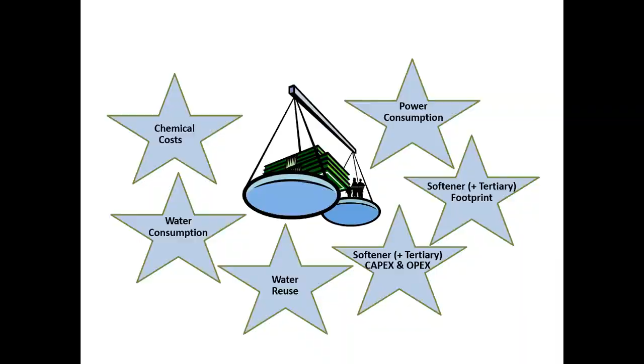Fine. If there are any questions, one can ask, or we can proceed to the other portion, filtration solutions, right? First, we were discussing the treatment part. The treatment part is basically for dissolved solids or TDS, or in case of scaling, corrosion, biofilm. Those are dissolved things in the water. That is one part of the topic, and the second part is filtration, which is for total suspended solids. That was for dissolved solids, and this is for suspended solids. Water treatment and filtration actually go hand in hand, so if we can adopt both practices, it will be beneficial for our cooling condenser systems, and they will work at design efficiencies.